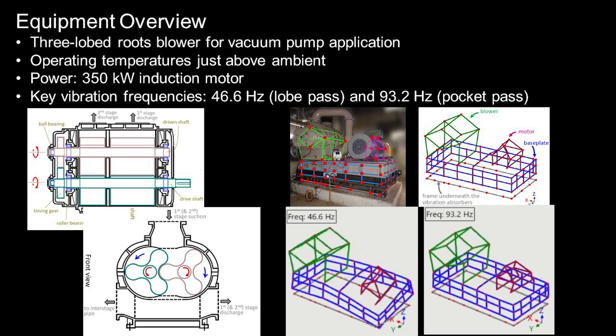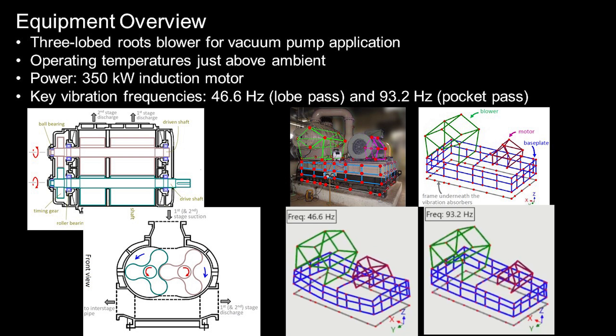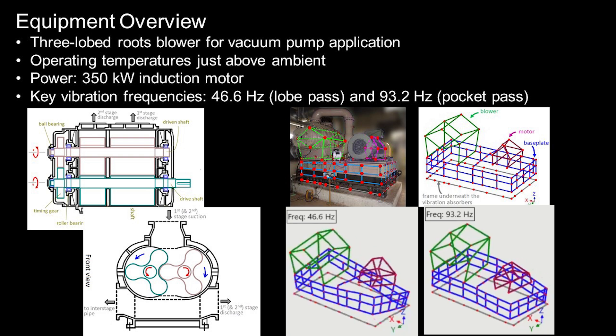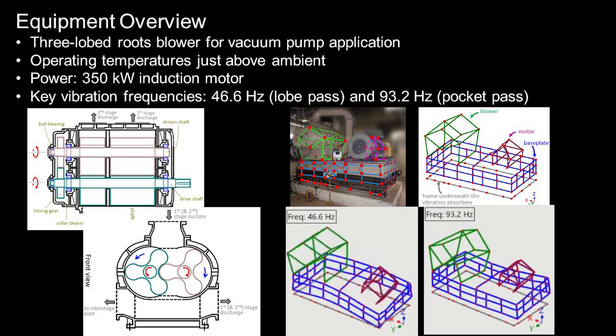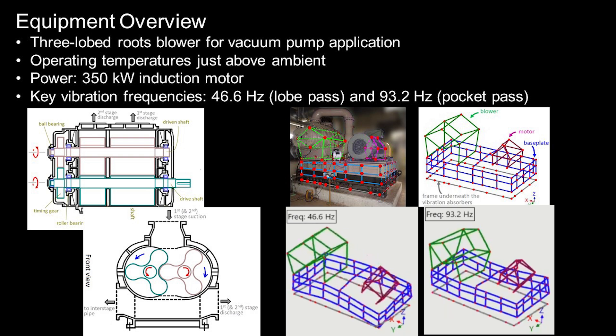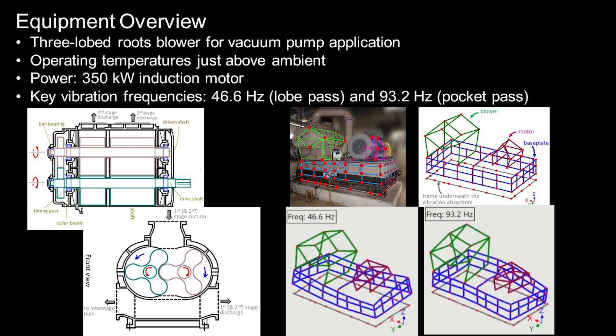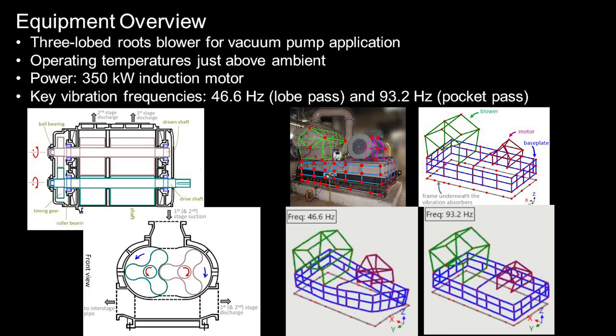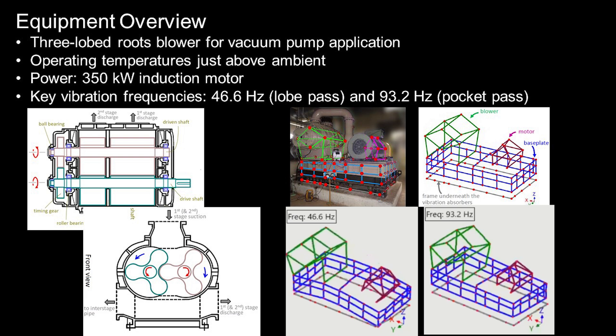This system has been repeatedly failing due to high vibrations, which occurred at two key frequencies: 46 Hz, which is lobe pass frequency, and 93 Hz, which is pocket pass frequency. These issues were primarily affecting the blower's bearings, drive shafts, side cover, internal partition wall, and base plate.